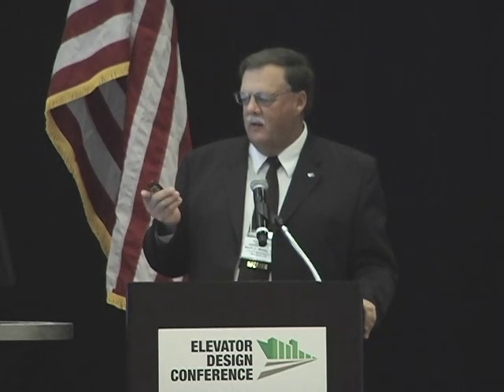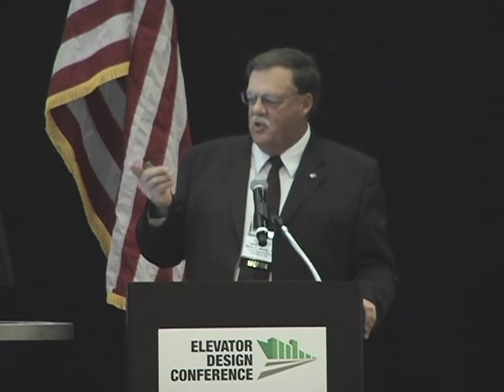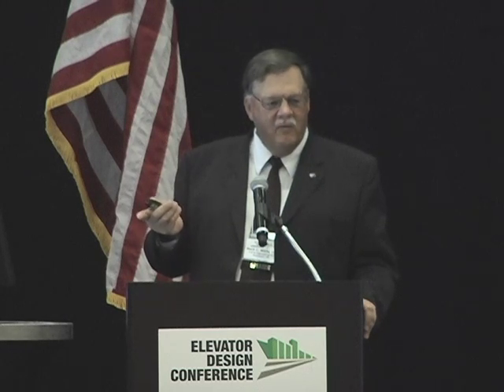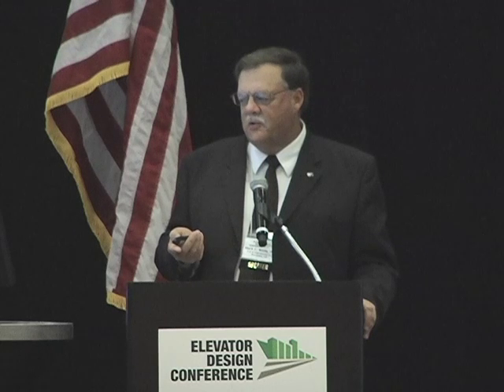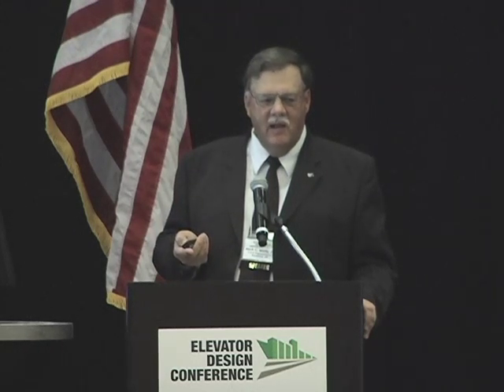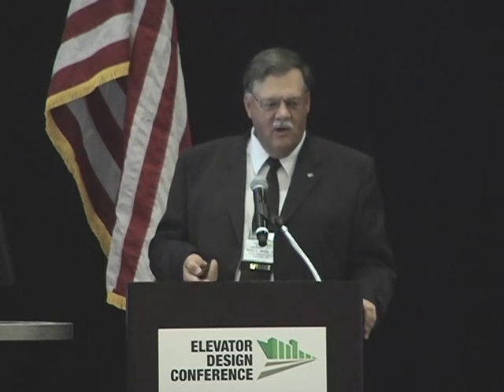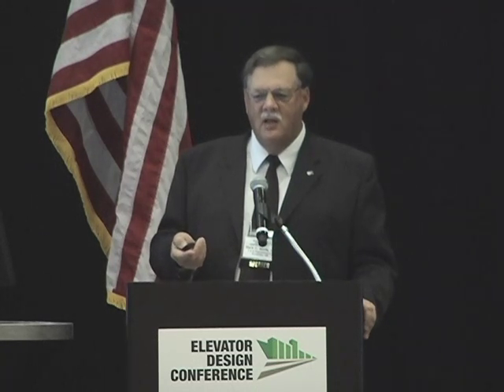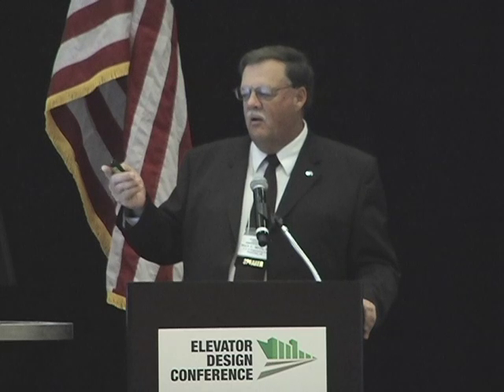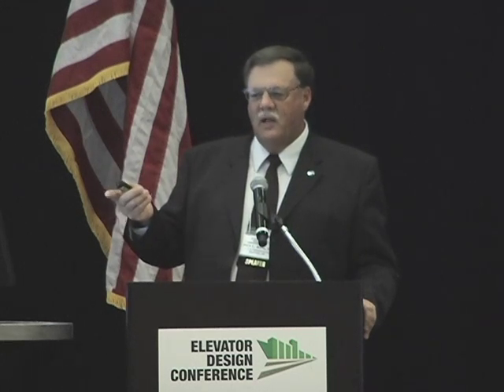Even if we have to run a 480-volt circuit a ways, some people will just put in an MCC and take a connection off the motor control center to feed your transformer for lighting or controls. I like to be able to shut that MCC down and work on it. If you've got issues with your process equipment, your conveying, your motors, it's nice to be able to shut down your process equipment and still have your lights on. And it's just a basic planning thing.